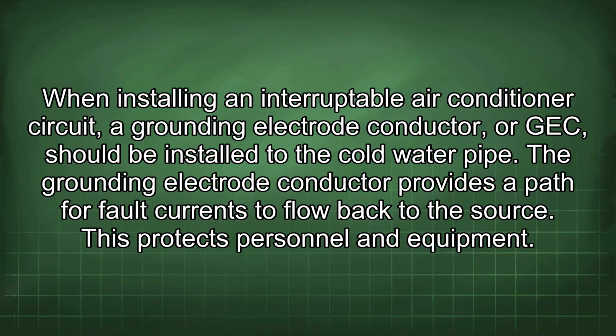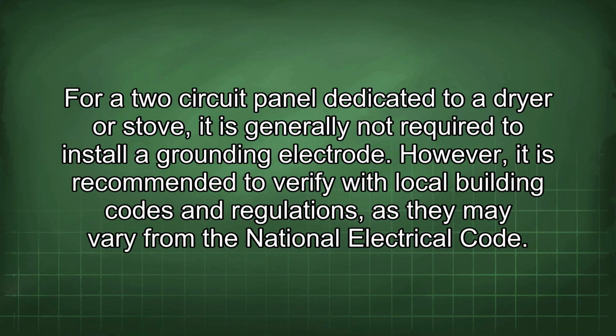When installing an interruptible air conditioner circuit, a grounding electrode conductor, or GEC, should be installed to the cold water pipe. The grounding electrode conductor provides a path for fault currents to flow back to the source. This protects personnel and equipment. For a two-circuit panel dedicated to a dryer or stove, it is generally not required to install a grounding electrode.